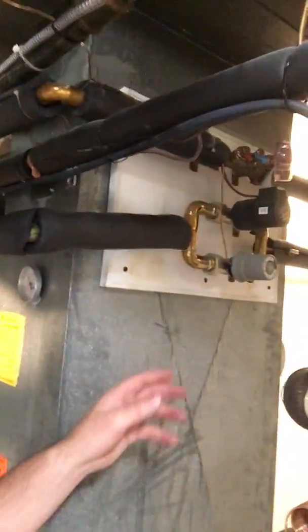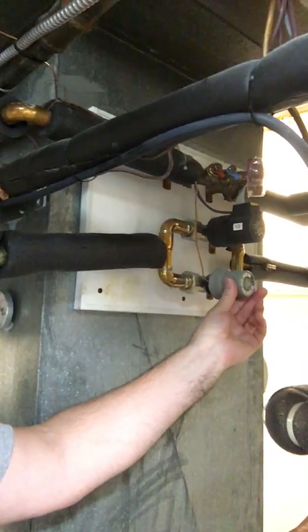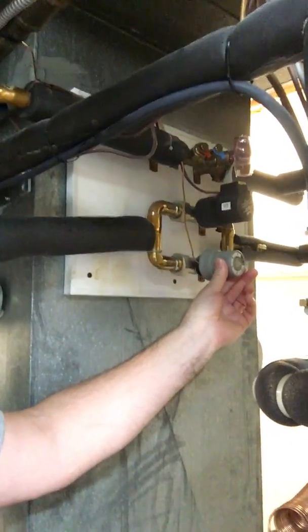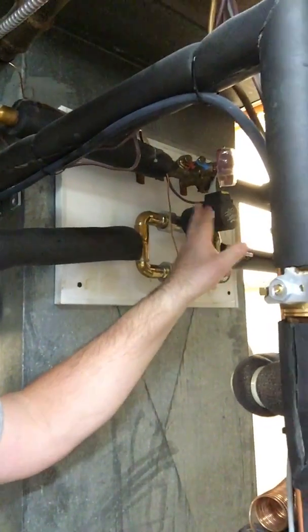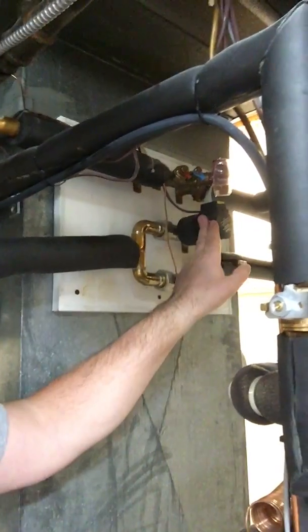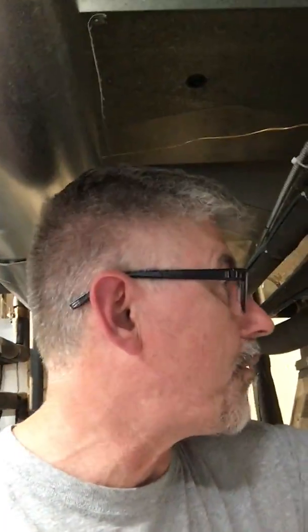Now the second fan coil is for the west side of the house, for the main floor and the upper areas other than the radiant floors that we have up there. And we use the same control system here. And this again is controlling the discharge air temperature for makeup air, and then this is the space control. So what this is actually connected to is not the second stage, but the first stage. So it does the first stage heat for that area. And then again, the balancing valves on all of the returns. So that's really important.